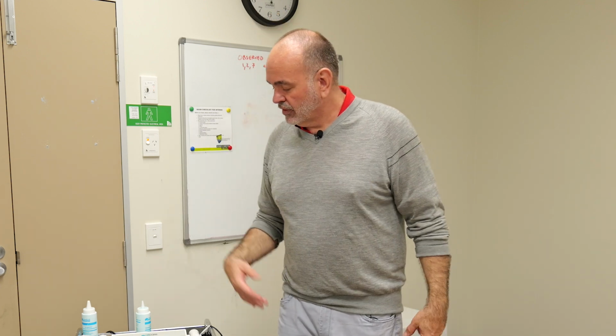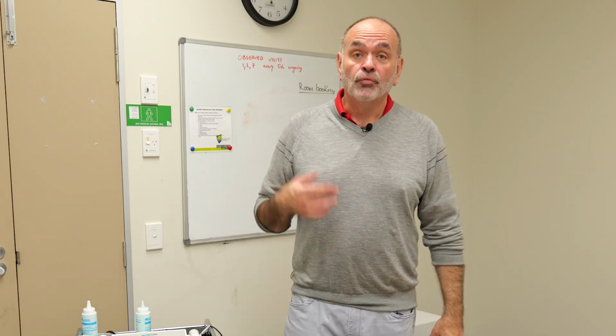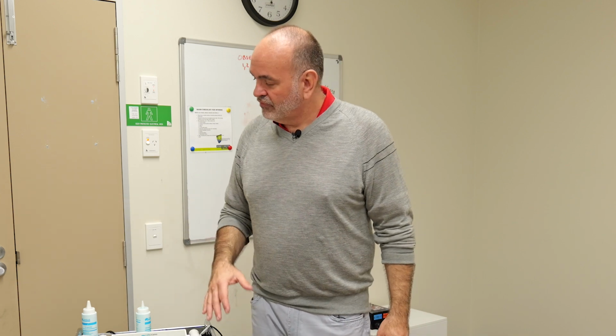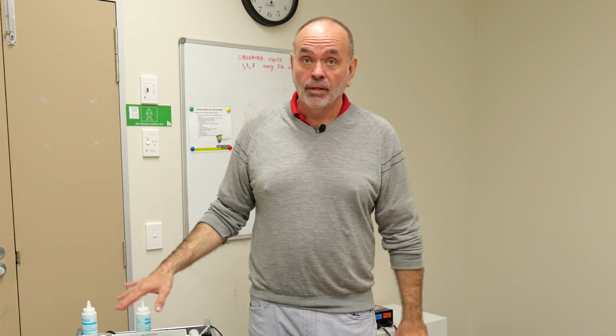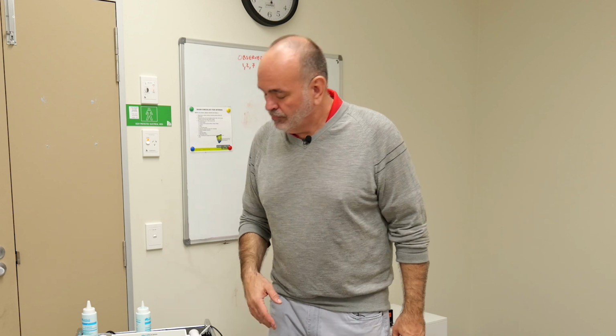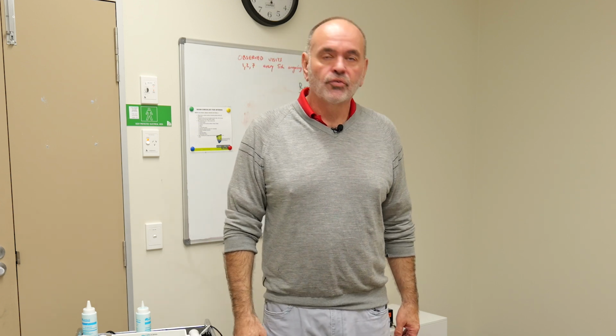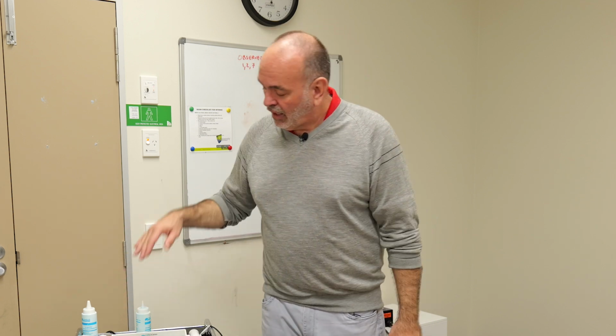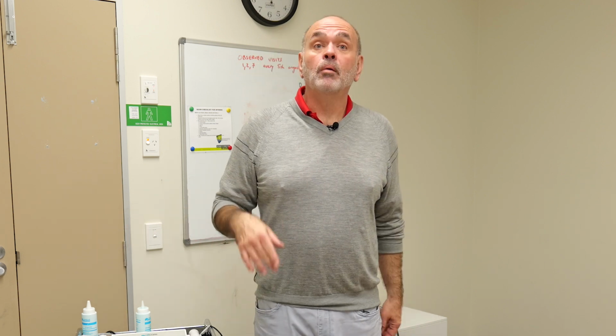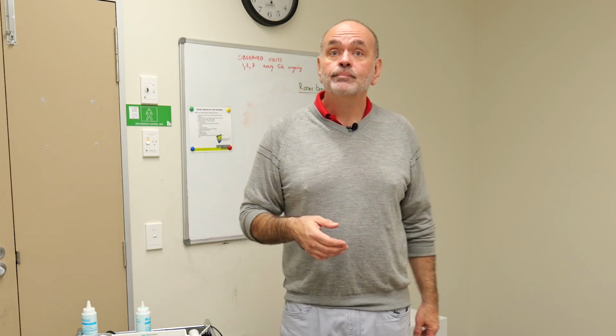And that's sort of the standard that we work on. So for small structures, we usually stay between 0.5 watts per centimeter squared and 1 watt per centimeter squared. And for larger structures, we may go a little bit higher in terms of the power, somewhere between 1 and 1.5 watts per centimeter squared. Now, the higher that we set the watts per centimeter squared means the more heat we're going to generate.